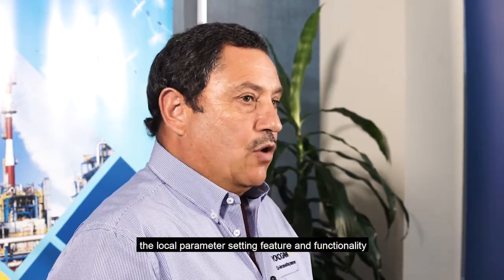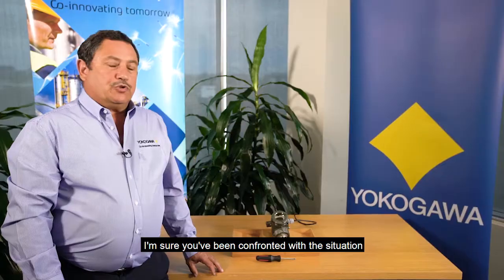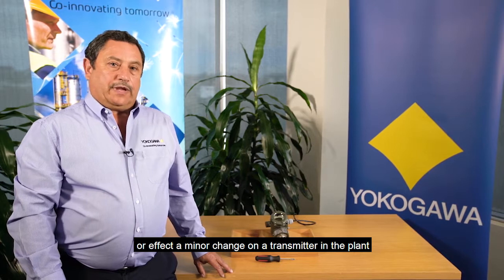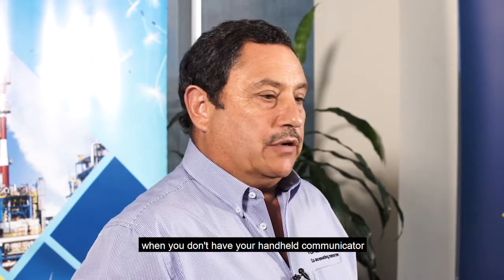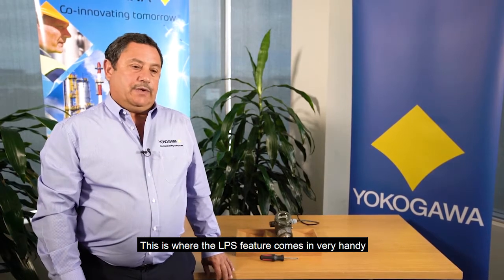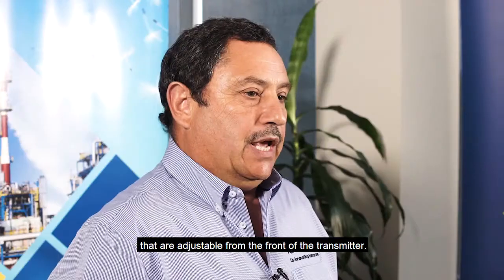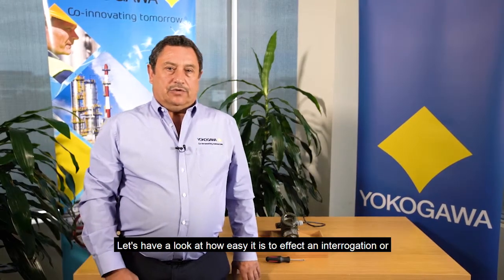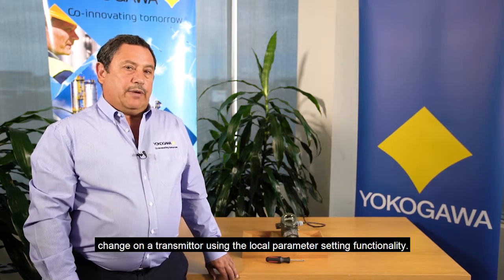Today I'm going to demonstrate the local parameter setting feature and functionality on the EJX and EJA transmitters. I'm sure you've been confronted with a situation where you've either got to interrogate a transmitter or effect a minor change on a transmitter in the plant when you don't have your handheld communicator or your field mate readily available. This is where the LPS feature comes in very handy as it allows access to the nine most important parameters that are adjustable from the front of the transmitter. Let's have a look at how easy it is to effect an interrogation or change on a transmitter using the local parameter setting functionality.